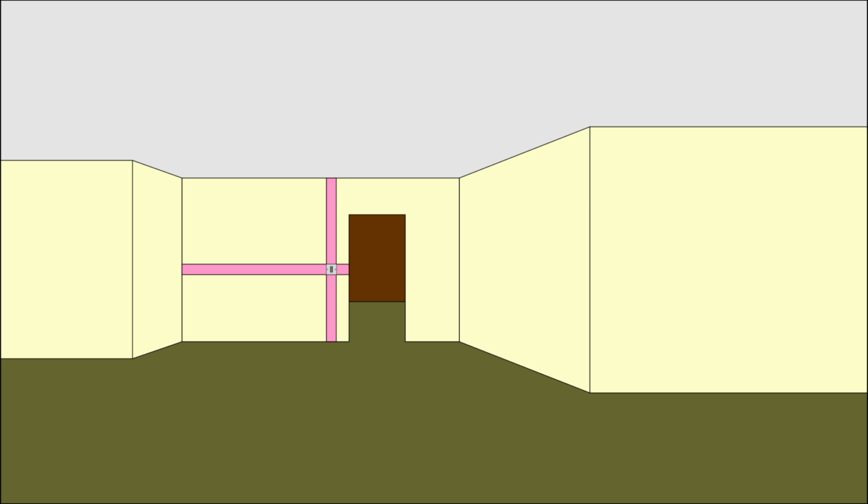But as before, as long as the cables are connected to the switch in this example, they can go either vertically above, below, or to the left or the right. It doesn't really matter which one it is, and again you just pick whichever is most convenient. Typically it's going to be above for a light switch, obviously because the cables are going up into the ceiling for the light. But again, it may be below, certainly for, say, upstairs, if it had a switch which controlled some lights on a downstairs hallway or something, then you may want to have them below, or in some cases above and below. And it's not entirely unlikely that you might want to put them horizontally.